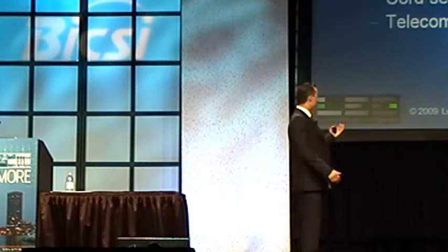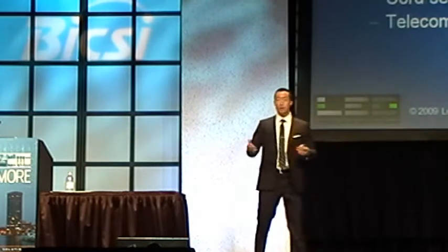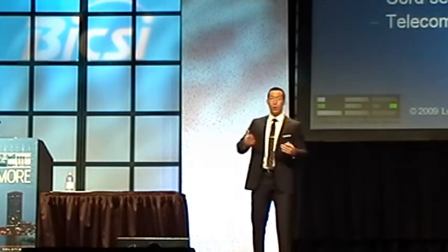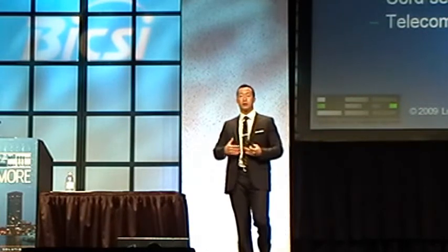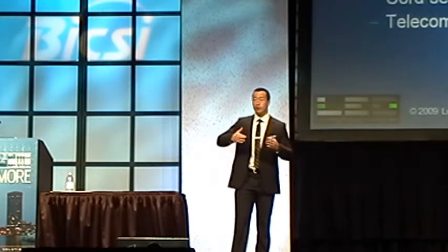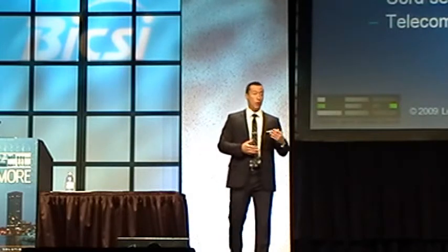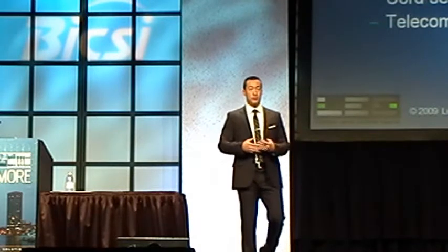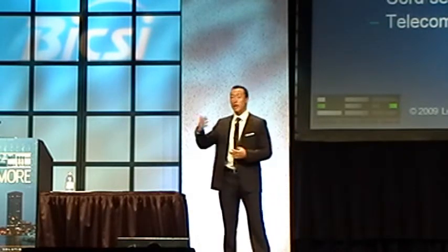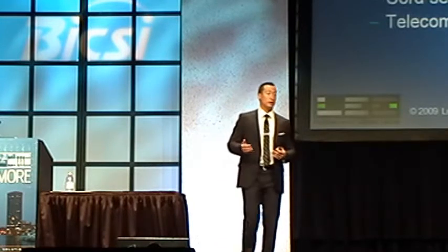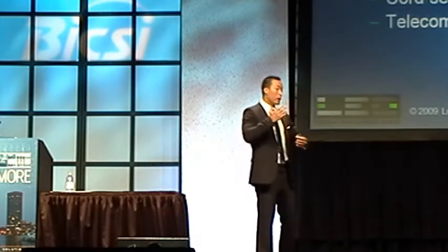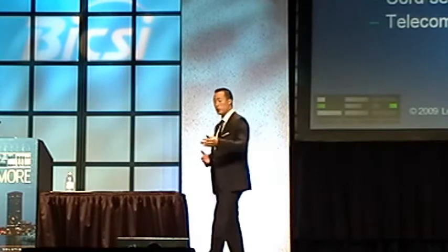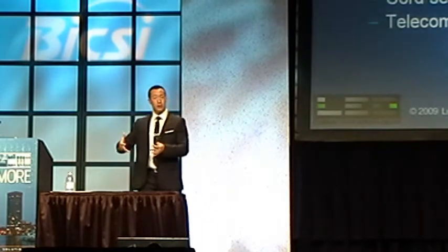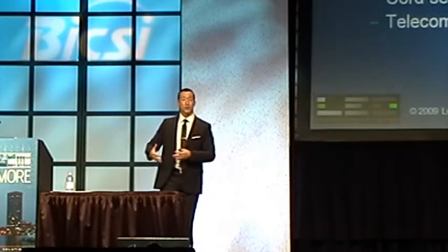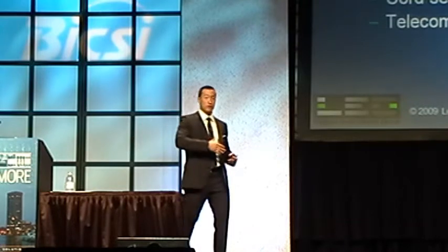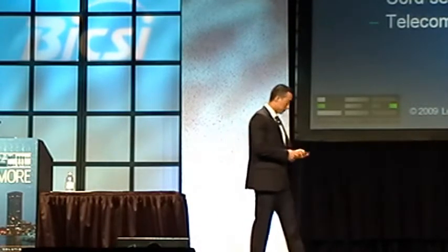We also want to include telecommunications connections. There's a large disparity between what equipment requires, especially at the server or equipment level, from piece to piece. A Windows server might need one copper Cat6 connection, while a SAN might need 24 LC duplex fiber optic connections. It varies from each piece of equipment, and we need to understand this at this stage so we don't under- or oversize the rack connections from a fiber and copper level.